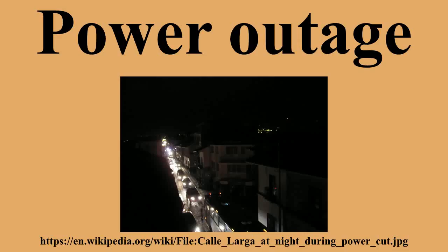Restoring power after a wide area outage. Restoring power after a wide area outage can be difficult, as power stations need to be brought back online. Normally, this is done with the help of power from the rest of the grid. In the total absence of grid power, a so-called black start needs to be performed to bootstrap the power grid into operation. The means of doing so will depend greatly on local circumstances and operational policies, but typically transmission utilities will establish localized power islands which are then progressively coupled together.